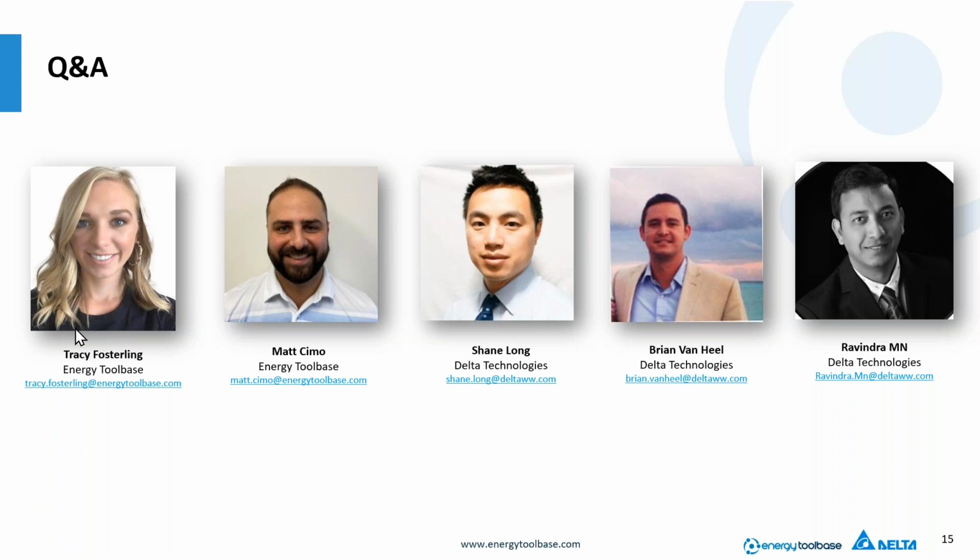Great, thank you, Matt. Delta, this is for you. You mentioned an outdoor system. What is that? Up to what temperature? This can operate from -20°C to +40°C operating temperature. It's a NEMA 3R outdoor system. If the temperature is above 40°C, it would derate, and we can provide the customer the derating curve, so you can see exactly what the output is at a certain temperature.